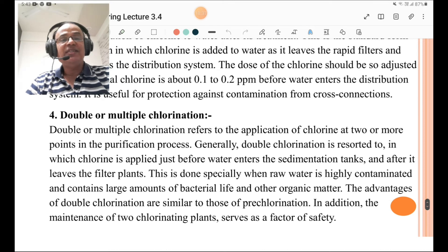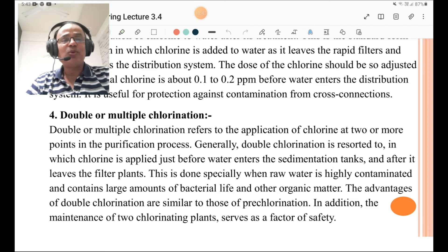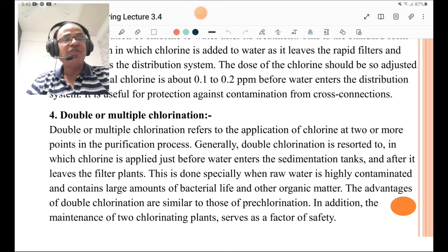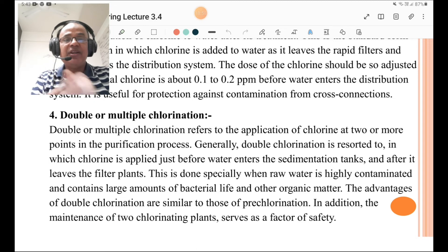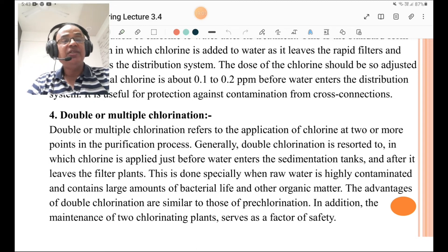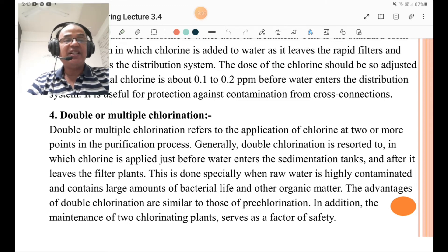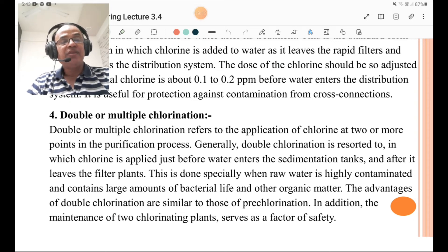Double or multiple chlorination refers to the application of chlorine at two or more points of the purification process. Generally, double chlorination is resorted to in which chlorine is applied just before water enters the sedimentation tank and after it leaves the filtration — that is, before sedimentation and after filtration. This is done especially when the raw water is highly contaminated and contains a large amount of bacterial life and other organic matter. The advantages of double chlorination are similar to those of pre-chlorination; in addition, maintaining two chlorinating plants serves as a safety factor.